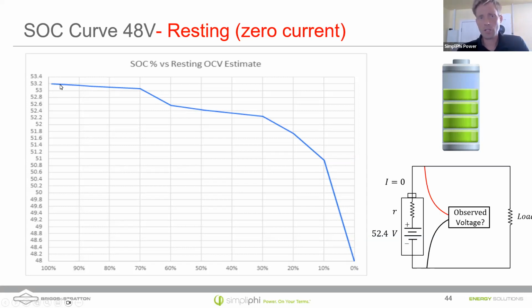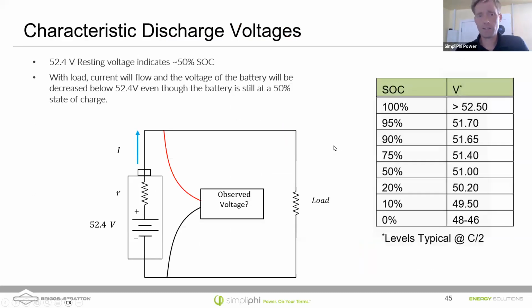And then as we discharge the battery and let it rest, you'll see that voltage drop off. So you can see at a 50% state of charge, a resting battery would have a voltage of about 52.4, 52.5 volts. Once we get down to a 10% state of charge, we're around 51 volts for a resting battery. It will be a lower voltage for a discharging battery. So I'm going to show you that in a second.